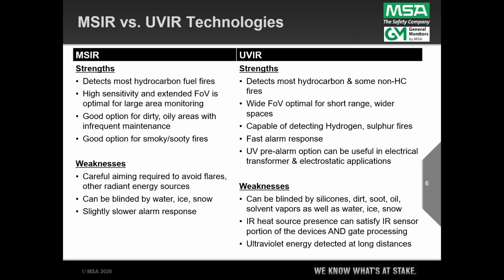And also, and this is true of any device on the market, any infrared detector, it can be blinded by water, ice, and snow. They absorb the infrared energy. They absorb the heat of a radiant flame. And that's the same for all of them out there. And because these MSIR devices are looking at 4 signals and doing some fairly sophisticated processing, they can require a little longer to create the alarm response in some cases, not all cases, but in some cases.